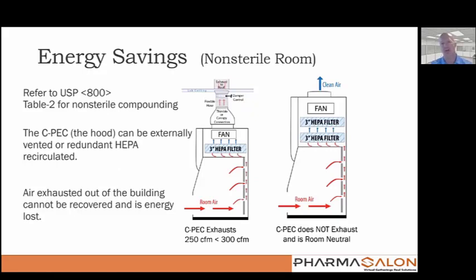So let's go from the sterile side over to the non-sterile side. Now, if you look at table two, it says that the CPEC, the containment primary engineering control, the hood, must be externally vented, or is preferred, or you can do redundant HEPA in series. I'm going to explain what that means here. If you connect your primary engineering control, your powder hood, via the manufacturer's thimble canopy to the external exhaust blower, which is that big contraption I showed you earlier, that's energy that is going out of the building. And yes, this hood is going to contribute to the overall negative pressure of the space.